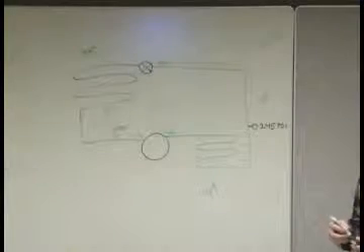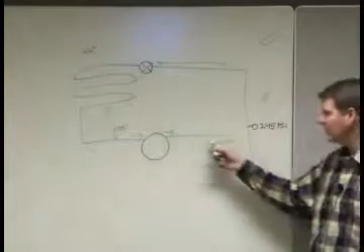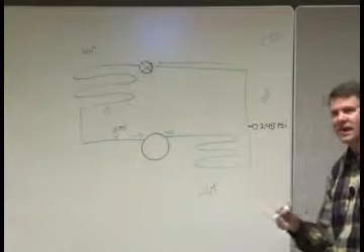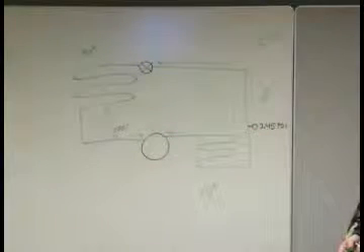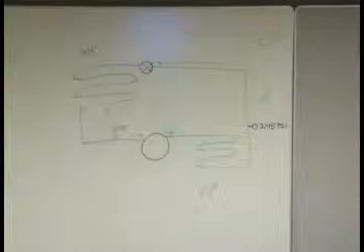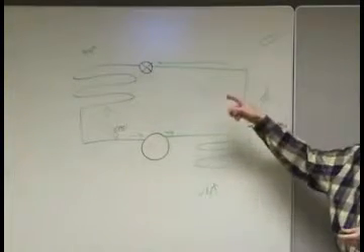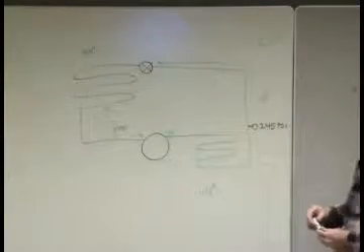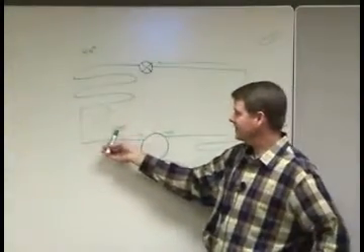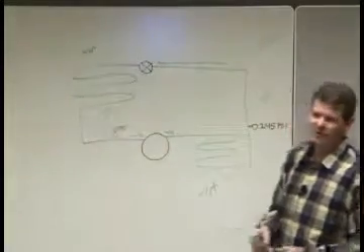It absorbs heat indoors, absorbs that latent heat indoors, comes back, we pump it up to change the boiling point, we boil it off, or condense it outside, boil it off inside. So we're absorbing heat indoors, and we're condensing it, giving it up outside. They use the refrigerant for obvious reasons. You couldn't use water because your temperatures would be way hotter than you want to be in your living room. So the great stuff about this is you can get this pressure down to 75 pounds and it boils at 44 degrees. So we can just boil it off in your house and just absorb the heat right out.